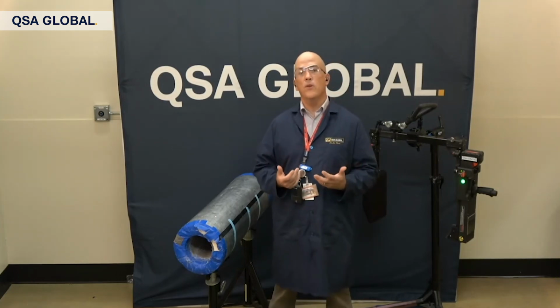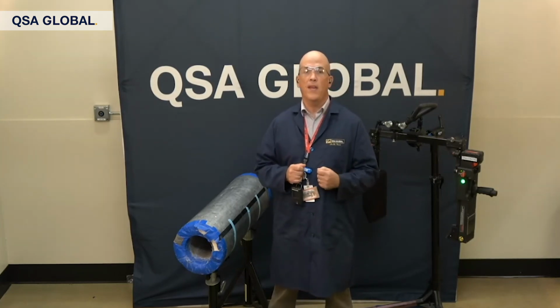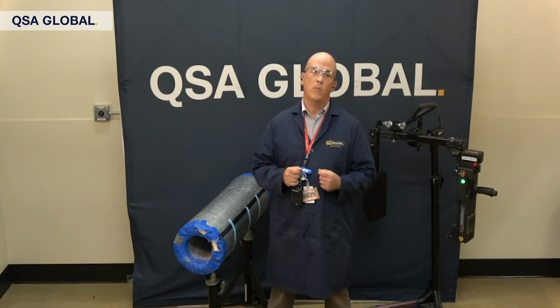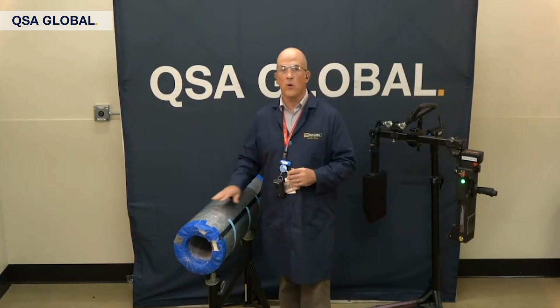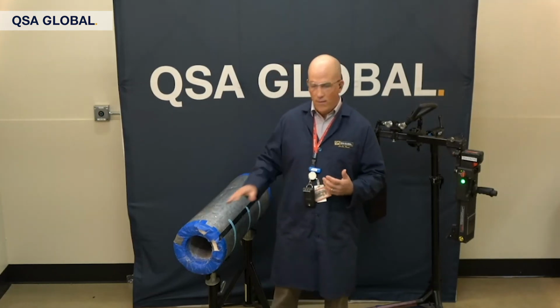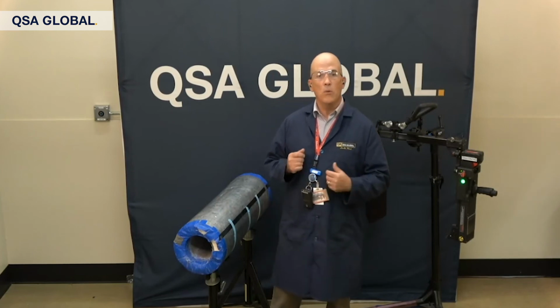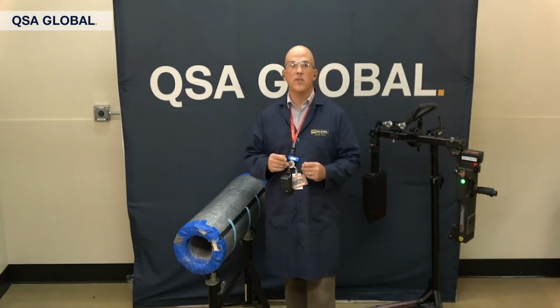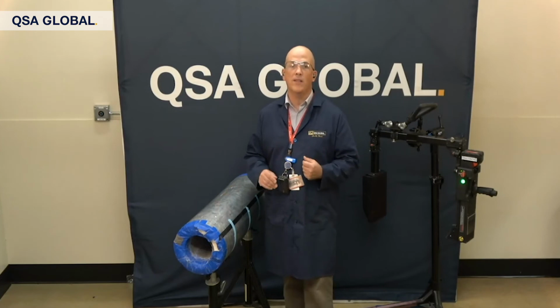Let's look at a few examples. Consider a plant in a tropical jungle environment where it rains so much that there's no chloride buildup on the piping, it just washes right off. However, you have insulated piping, so after that monsoon season, it would be ideal to go out there and assess the barrier and the sheathing to look for wet insulation and corrosion byproduct.